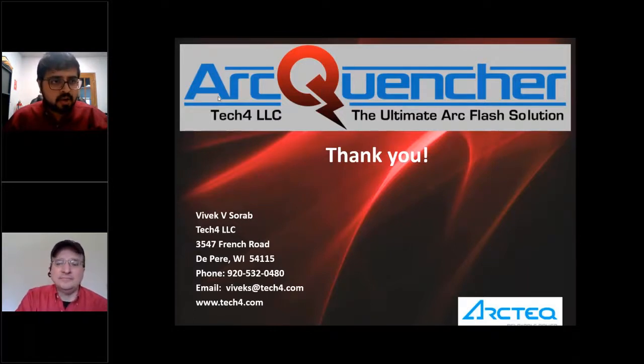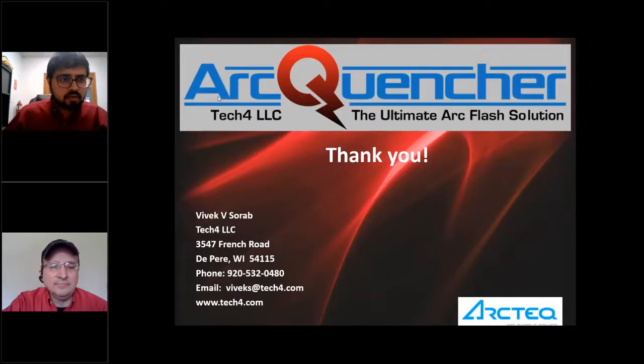If there are no more questions, hey, we have a question here, Vivek, and it's a very good question. It's on the operation of the arc quencher system. And it reads, will the arc quencher trigger if someone opens the switchgear door and takes a picture of the cubicle or bus inside? So no.